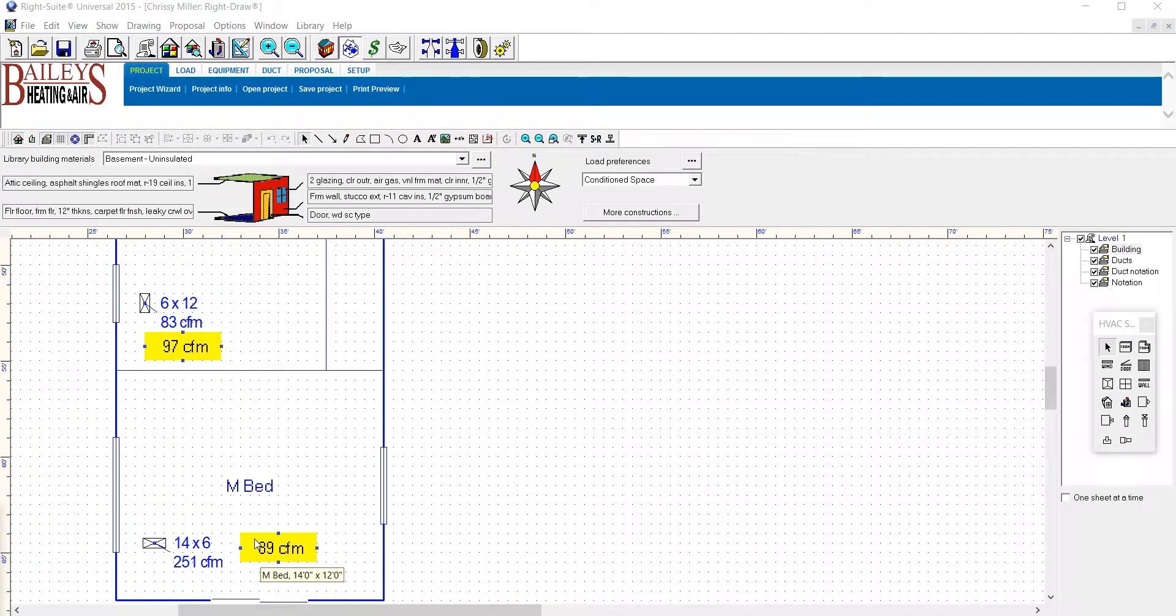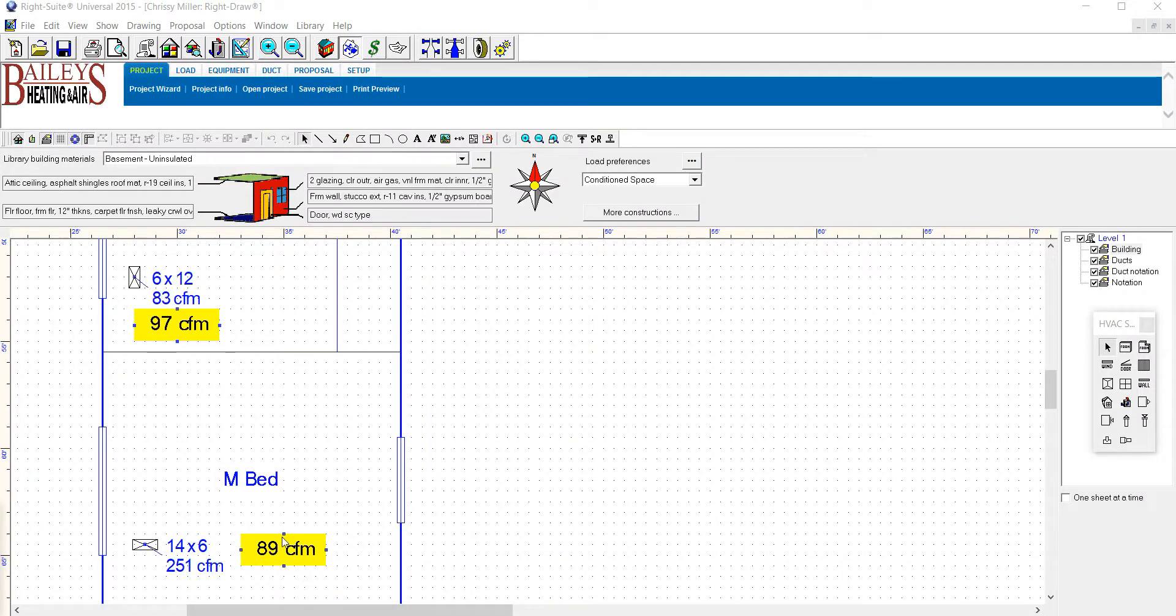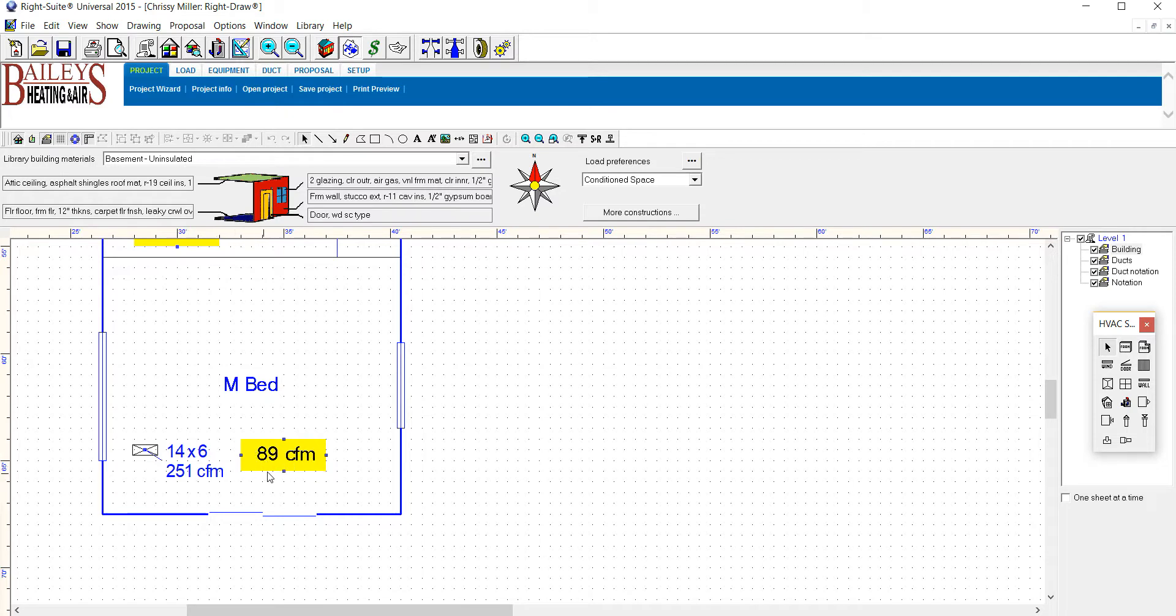So let me zoom in a little bit because this is that master bedroom we're having problems with. If we look at the master bedroom, the 89 CFM, that's the amount of air that's coming to the room - 89 cubic feet of air per minute. As you can see, it's not a lot and it's supposed to be 251 CFM.